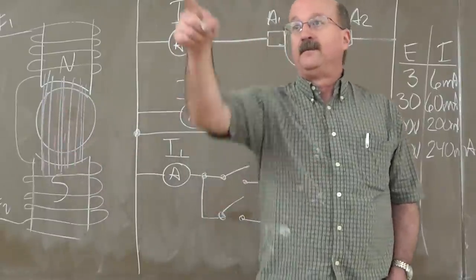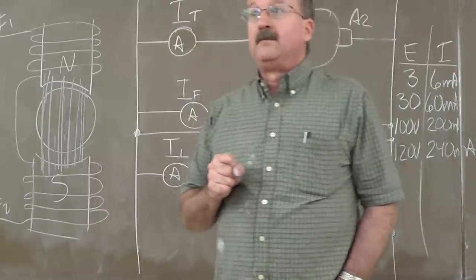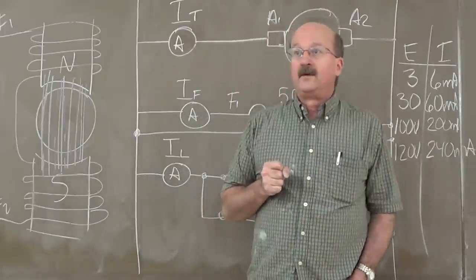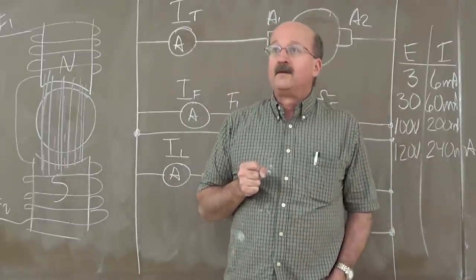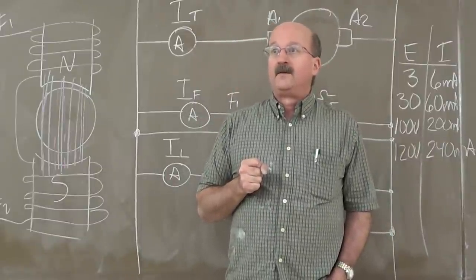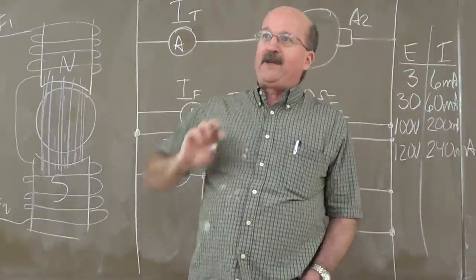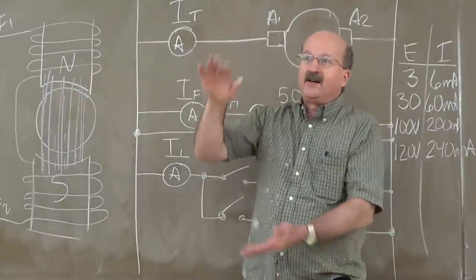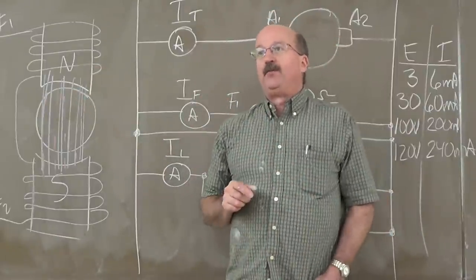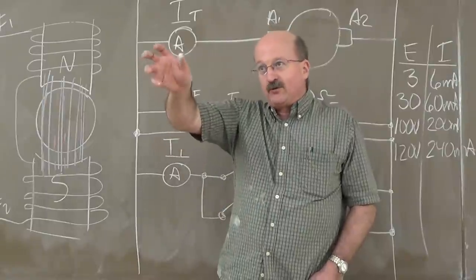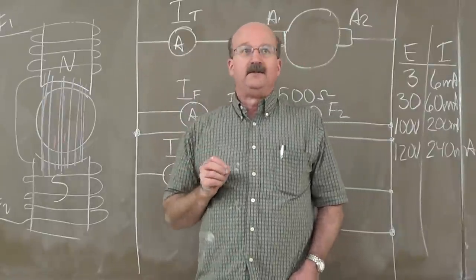Then it would fire back up. When you said that the field collapses, if the voltage is reduced quickly, the polarity changes, correct? You can, under certain conditions. If you drop that field real quick, it can collapse and cause it to polarize in the opposite direction. That's why we have you lowering it slowly.